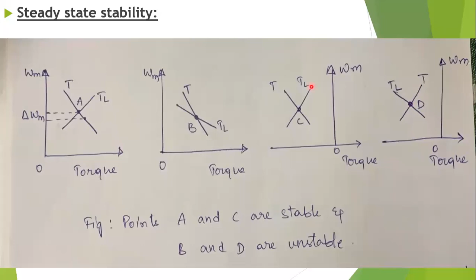From this, if you see, an equilibrium point is stable when the speed increases. This increase in speed causes load torque to be greater than motor torque. The conditions at the equilibrium point we will see in the next slide. So an equilibrium point is stable when an increase in speed causes the load torque to exceed the motor torque. At equilibrium the following condition is satisfied: dTL by d omega m is greater than dT by d omega m.